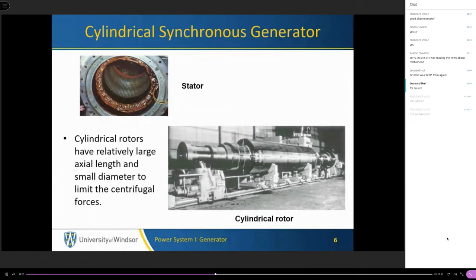Now let's look at the construction. I told you the stator is common between the round and the salient pole, but the rotor has to be manufactured long, very long, to limit the centrifugal forces. I told you this type of machine runs at high speeds, so to limit the centrifugal forces, you have to build the rotor to be long.